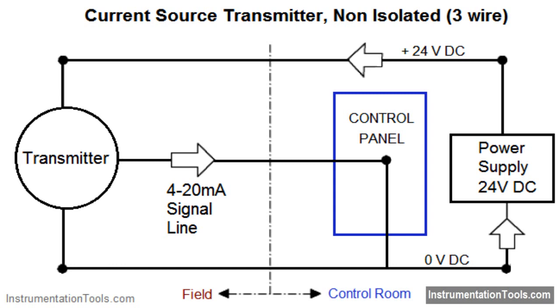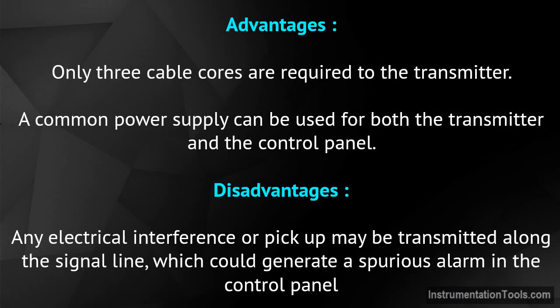Three-wire current source transmitter non-isolated. This is the most common configuration of modern 4 to 20 milliamps transmitters. The transmitter and control panel can use the same 24 volts and 0 volts DC supply lines. The 4 to 20 milliamp signal flows through the 24 volts DC line and the signal line to the controller. Advantages: only three cable cores are required to the transmitter.